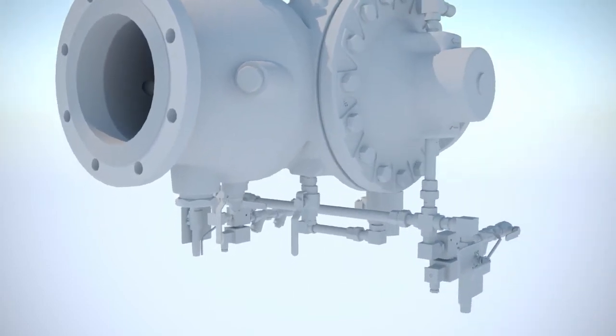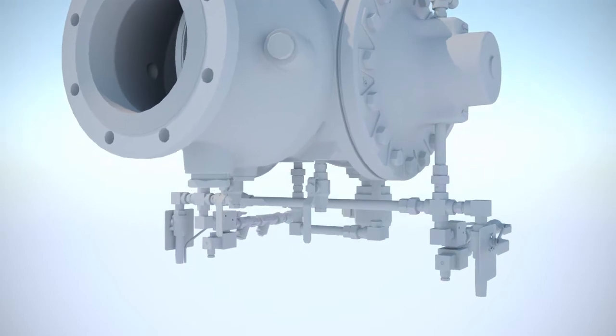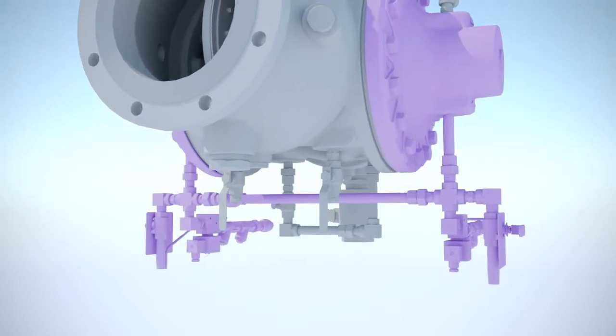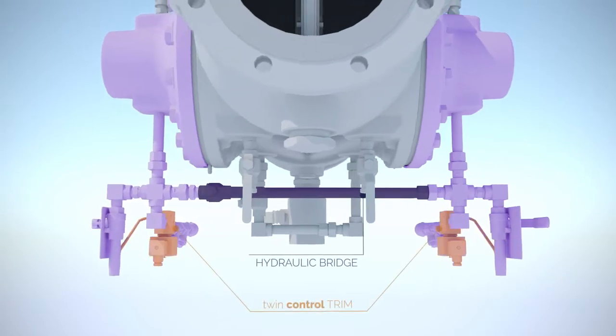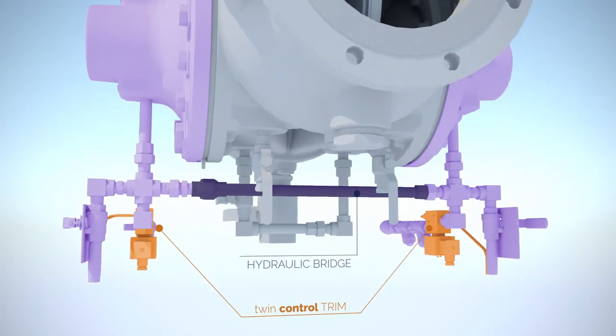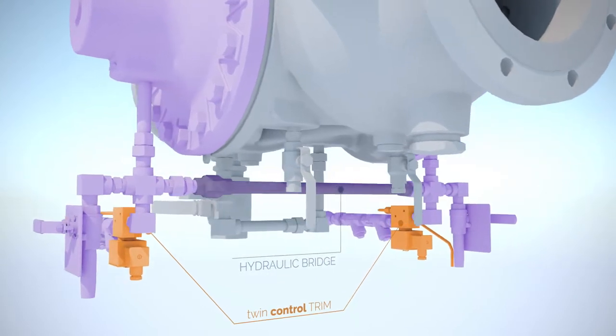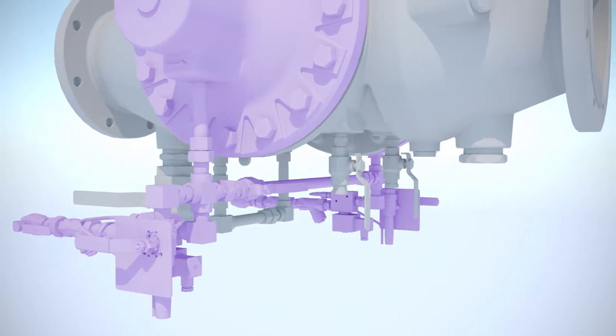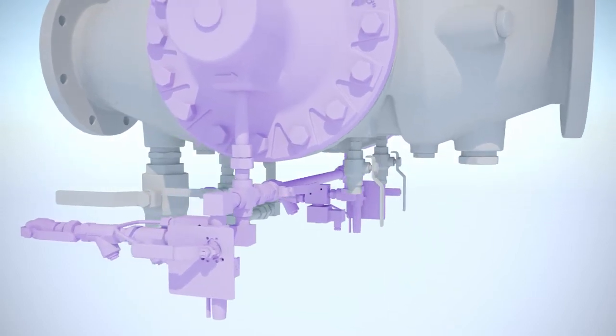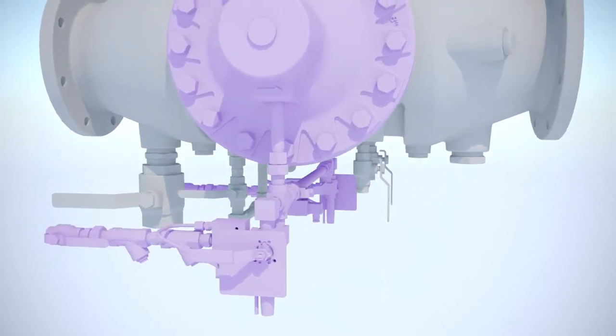Following on from the redundancy principle applied to the two control chambers, the VDD is also equipped with a twin control trim which actuates each of the two chambers. The two trims are linked by means of a hydraulic bridge which propagates any activation trim to either of the two chambers to form a deluge system with an integrated bypass line.